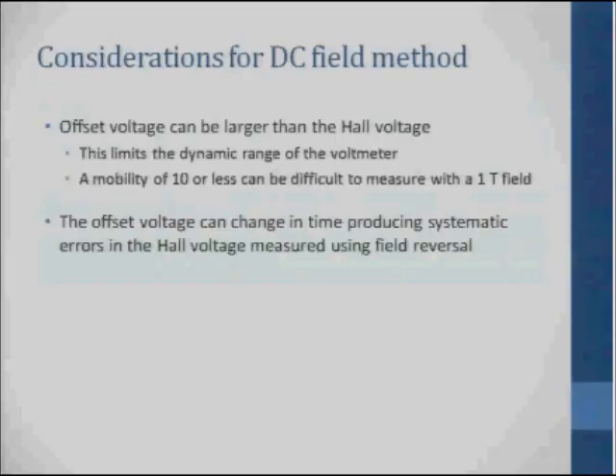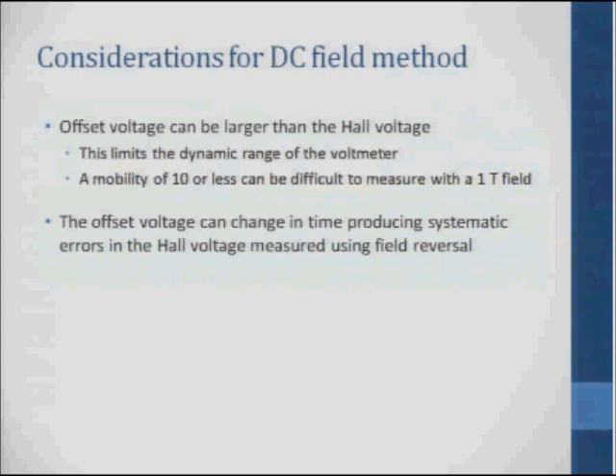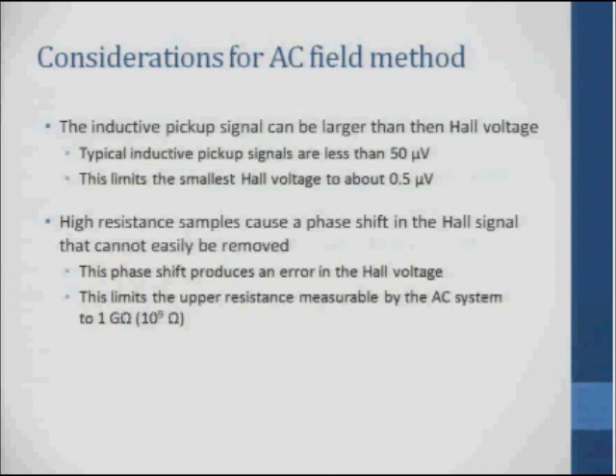To wrap up and review: with the DC field method, offset voltages can be much larger than the Hall voltage, which limits the dynamic range of the voltmeter. Practically, a mobility of 10 or less can be difficult to measure with fields up to one Tesla. Increasing the current in a DC measurement increases both the misalignment voltage and the Hall voltage proportionally, so it doesn't really buy you more dynamic range on the voltmeter. The misalignment voltage can also change in time, producing systematic errors in the Hall voltage when using field reversal. For the AC method, ultimately the inductive pickup is going to limit your sensitivity, so you want to keep that as small as you can.